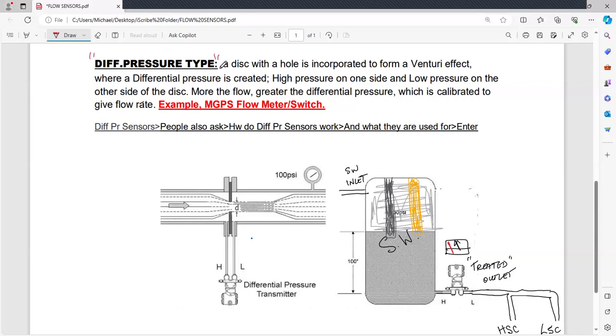Now, how is this type of flow meter going to work? Remember when we were doing the differential pressure transmitter? Okay, it's going to be exactly like that. So one side, you will be having that permanent plate. And again, on the other side, you will be having a permanent plate. Okay, and in between, you're going to have that diaphragm. So this is going to act as one capacitor. This is going to act as one capacitor. And then the differential between capacitor 1 and capacitor 2, that is going to be giving you your particular flow rate. Instead of getting the capacitance, that particular connection will be connected to your meter over here.